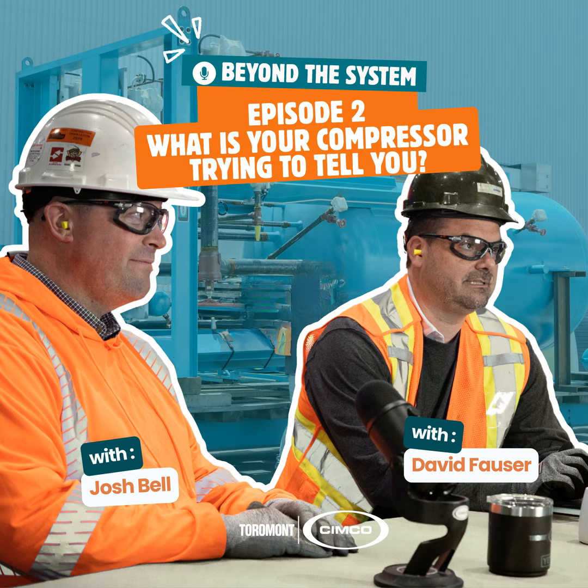Without it, you have to critically control your refrigerant flow through, say, a direct expansion type loop, which can put the compressor at risk, especially bigger compressors. They require superheat to protect them. The superheat ensures there's no liquid left in the vapor stream. And when we're talking about ice rink application or industrial refrigeration, often the band is so tight. We don't carry a lot of superheat over to the compressor, often zero, and we need those vessels there to protect from any liquid getting into the compressor. So, it's basically, as you mentioned, a pump for the system in the most simple terms, but very critical.